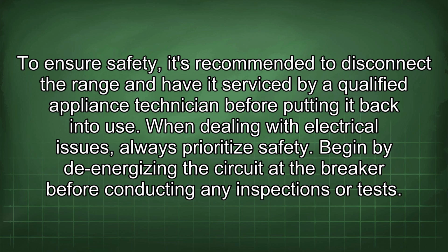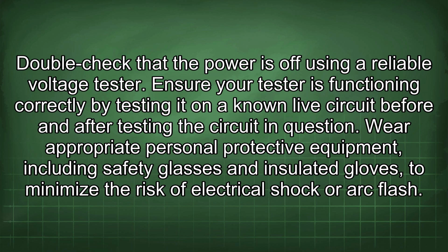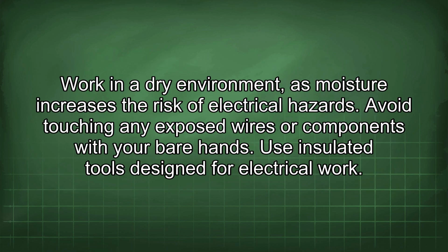Begin by de-energizing the circuit at the breaker before conducting any inspections or tests. Double-check that the power is off using a reliable voltage tester. Ensure your tester is functioning correctly by testing it on a known live circuit before and after testing the circuit in question. Wear appropriate personal protective equipment, including safety glasses and insulated gloves, to minimize the risk of electrical shock or arc flash. Work in a dry environment, as moisture increases the risk of electrical hazards.